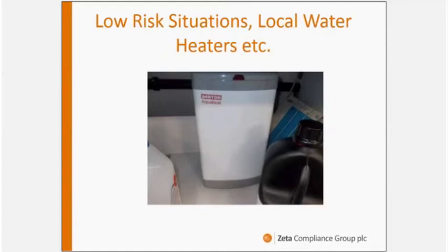So, in terms of linking those two together, if you've got an electronic logbook like ZetaSafe, or indeed just paper logbooks or whatever, it looks like you're going to have to amend your control schemes to firstly take account of more sentinel points, if you've got a complex circulating hot water system, and maybe you could relax things where you've got this definition now of a low risk situation. Yes, I think there's a change in scenery with the change in the guidance. Yes, the new definition of a sentinel point will pick up on the configuration of the system in a way that previously it wasn't. It's an example of applying the competence, understanding the system to bring the risk down, and the same applies with the low risk systems.